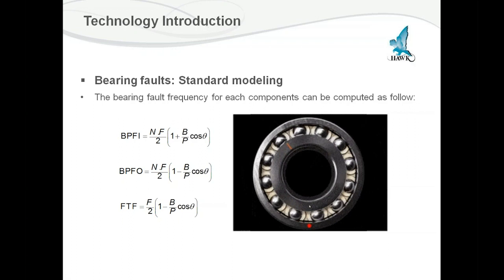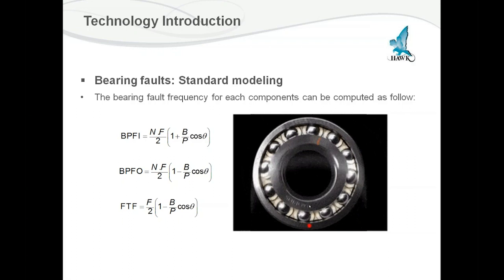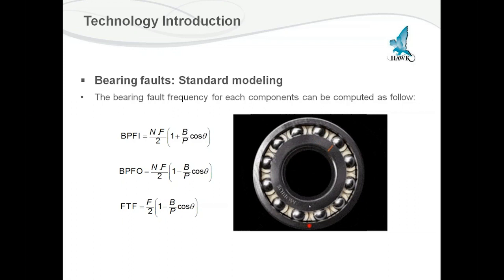The speed of rotation is based on the roller size and the belt speed. So there are different factors we take into consideration with our analysis, and we look for fundamental frequencies that are known to be associated with rollers of that make and size. If you were to do a project like this with us, I would ask for the bearing type you're using and probably samples to bring back to base, which we would take apart, have a good look at and take measurements from. Those small measurements on the actual bearing itself are the critical ones.